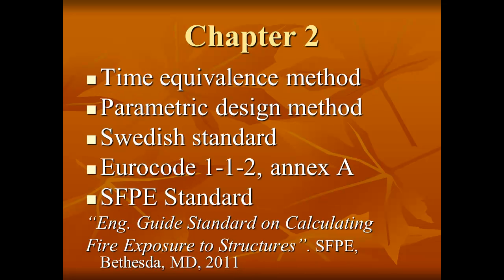Chapter 2 presents an overview of the main simplified methods of obtaining the structural fire load at the present time: the time equivalence method and the parametric design method. The parametric natural fire model considers the actual boundary conditions of the fire compartment concerning fire load, ventilation conditions, geometry, and thermal properties of enclosure. These curves have been incorporated into a Swedish standard and have also served as the basis for the parametric temperature-time curves of Eurocode 1-1-2. It also includes an overview of the SFPE Standard Engineering Guide on Calculating Fire Exposures to Structures, 2011.